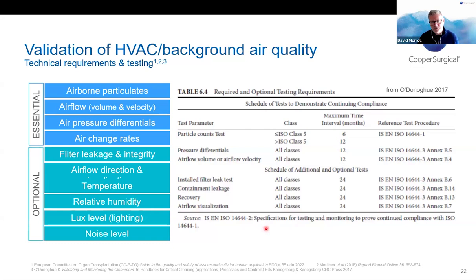Now this is targeted much more towards standard clean rooms, so that's the caveat that I would say to this, but I think it's still applicable. And what it says is that the essential elements of your validation of your air quality monitoring are the particulates, as you would guess, because it's numbers of particulates that dictate the grade, airflow, so the volume and velocity, the air pressure differentials, and the air change rate. So this is fairly standard stuff for clean rooms, just thinking about the cleanliness of the air and how often it's changed, and whether you've got a positive pressure in your embryology lab.